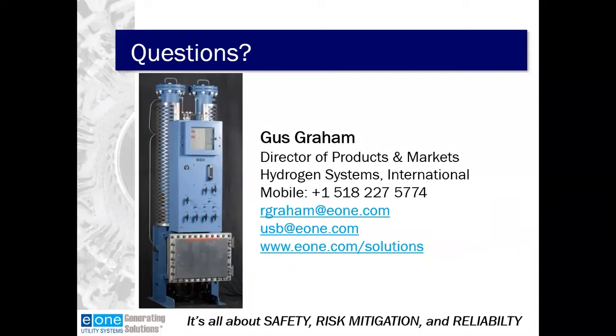So if you're going to switch from a CO2-based purging system to a nitrogen-based purging system, obviously the first thing you want to do is consult your generator OEM and make sure that all of the appropriate boxes are checked there. But then, looking deeper into the design of your system, the hydrogen purity analyzer needs to be considered: how you're going to detect the difference between air and nitrogen during your changeover procedure.